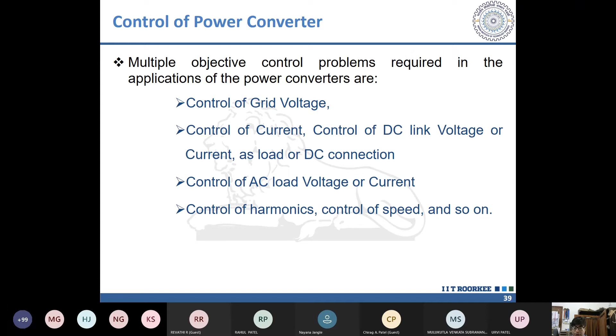Now, control of power converters is considered as control of voltage and current. Generally, it can be a current-controlled voltage source inverter. As we know, the power transfer equation is V1 V2 by X. Once you control the current, the inverter voltage will automatically change to accommodate the power, of course if it is available. Now here we can see one control logic. We use a concept called voltage mode control, which ensures that the voltage is maintained, and that is the strategy.